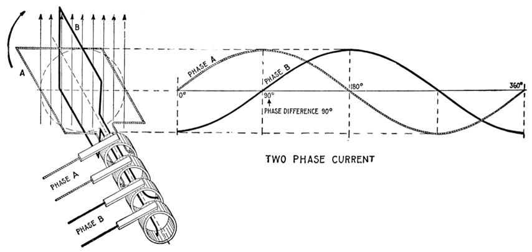Two-phase power can be derived from a three-phase source using two transformers in a Scott connection. One transformer primary is connected across two phases of the supply. The second transformer is connected to a center tap of the first transformer, and is wound for 86.6% of the phase-to-phase voltage on the three-phase system. The secondaries of the transformers will have two phases 90 degrees apart in time.